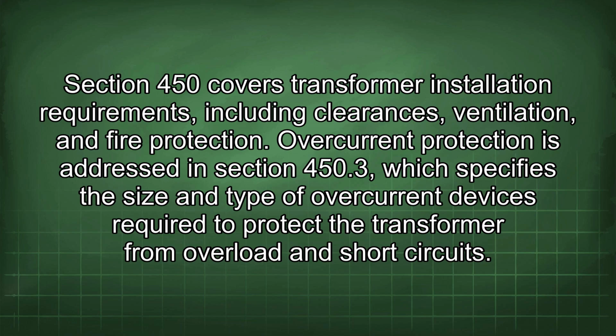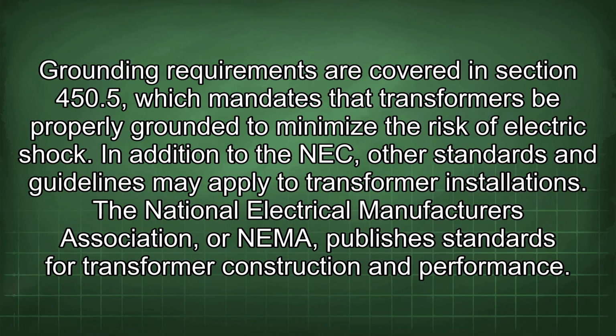Overcurrent protection is addressed in Section 450.3, which specifies the size and type of overcurrent devices required to protect the transformer from overload and short circuits. Grounding requirements are covered in Section 450.5, which mandates that transformers be properly grounded to minimize the risk of electric shock. In addition to the NEC, other standards and guidelines may apply to transformer installations.